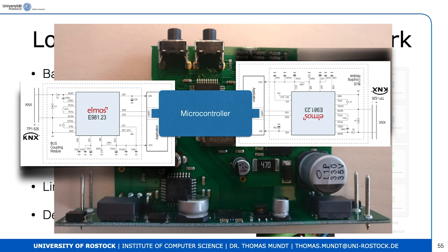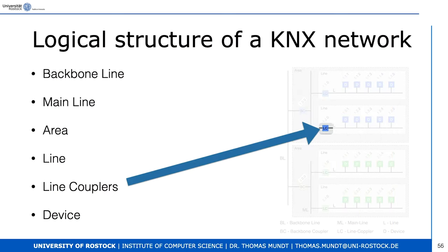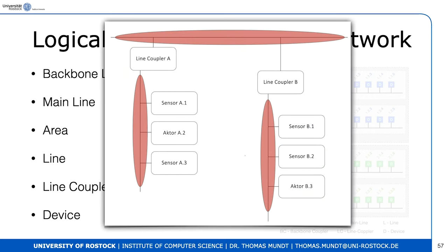The line coupler decides whether it forwards telegrams from one line to another based on rules in its memory. Line couplers form a broadcast domain — if someone sends a broadcast on a line, every device on that line can intercept, eavesdrop, and wiretap those telegrams. A line is a broadcast domain in KNX with twisted pair cabling.